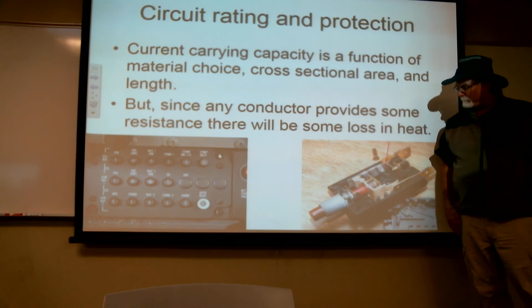So in the case of current carrying, it's always going to be a function of the choice of material, which for us isn't really a choice. We're always going to use copper. Occasionally there's aluminum, but pretty much copper. But it's really cross-sectional area and the length of the run. And the length of the run really is about the allowable voltage drop. If I use a smaller wire, I'm going to have a greater voltage drop.